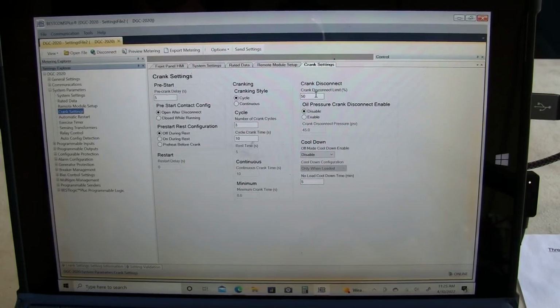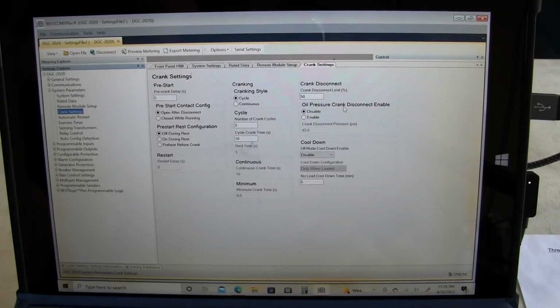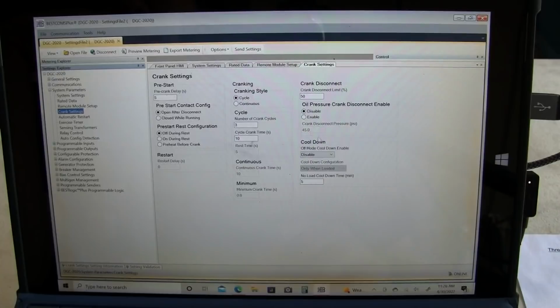Crank disconnect speed is 50% of rated. So once the engine hits 900 RPM, the starter will disengage. I have the oil pressure crank disconnect disabled. I had some issues with that. If the unit was cranking, but it was cold and it wasn't wanting to start, the oil pressure would build up past the threshold and it would just stop cranking.